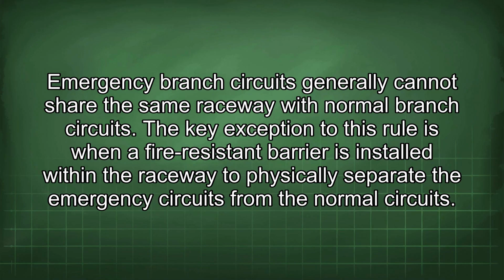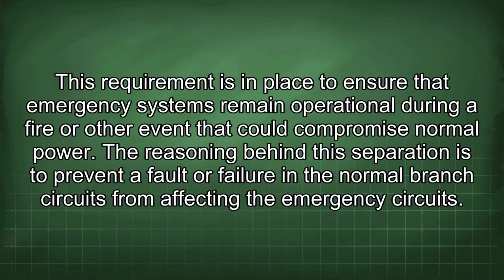Emergency branch circuits generally cannot share the same raceway with normal branch circuits. The key exception to this rule is when a fire-resistant barrier is installed within the raceway to physically separate the emergency circuits from the normal circuits. This requirement is in place to ensure that emergency systems remain operational during a fire or other event that could compromise normal power. The reasoning behind the separation is to prevent a fault or failure in the normal branch circuits from affecting the emergency circuits.